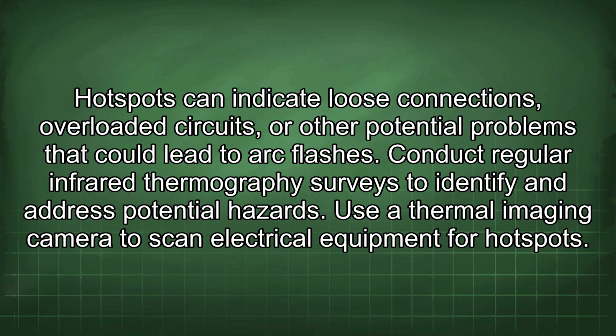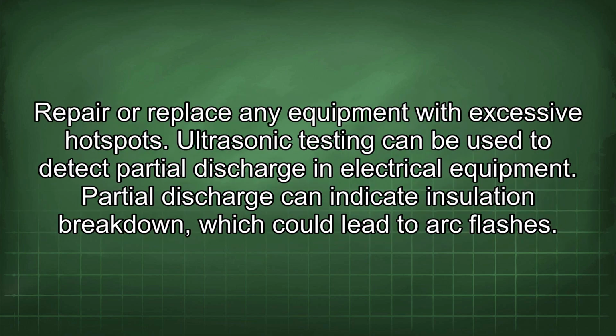Use a thermal imaging camera to scan electrical equipment for hotspots. Repair or replace any equipment with excessive hotspots. Ultrasonic testing can be used to detect partial discharge in electrical equipment. Partial discharge can indicate insulation breakdown, which could lead to arc flashes.